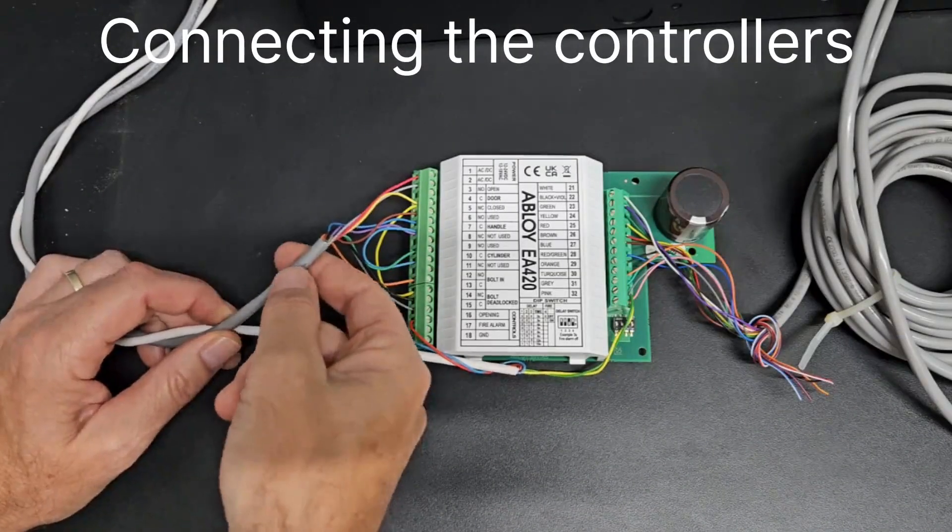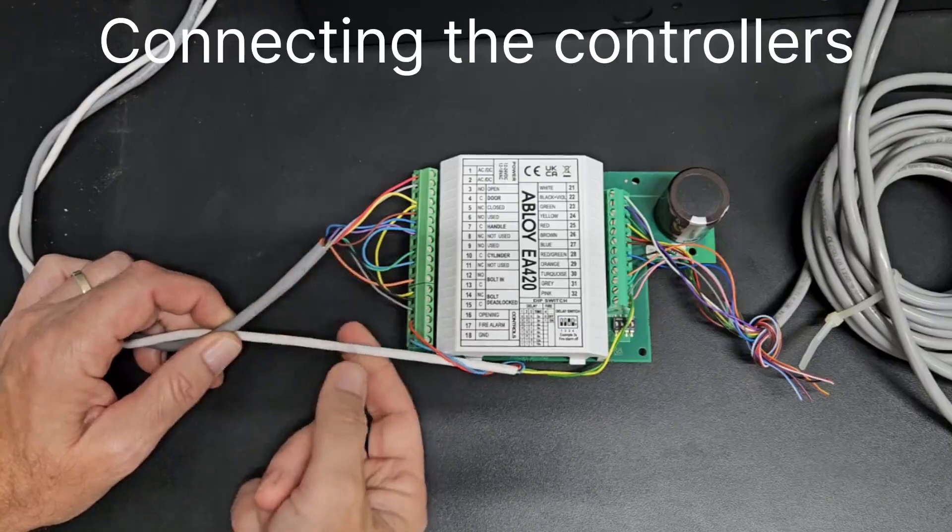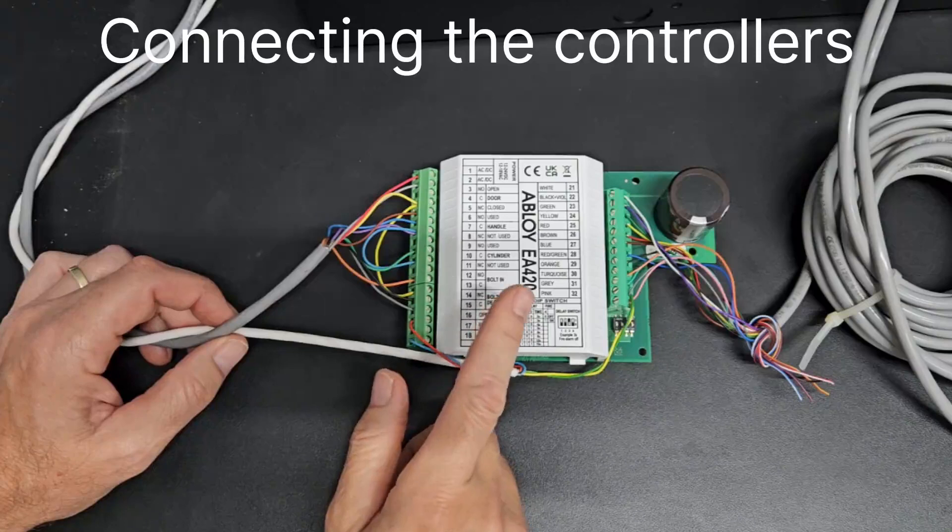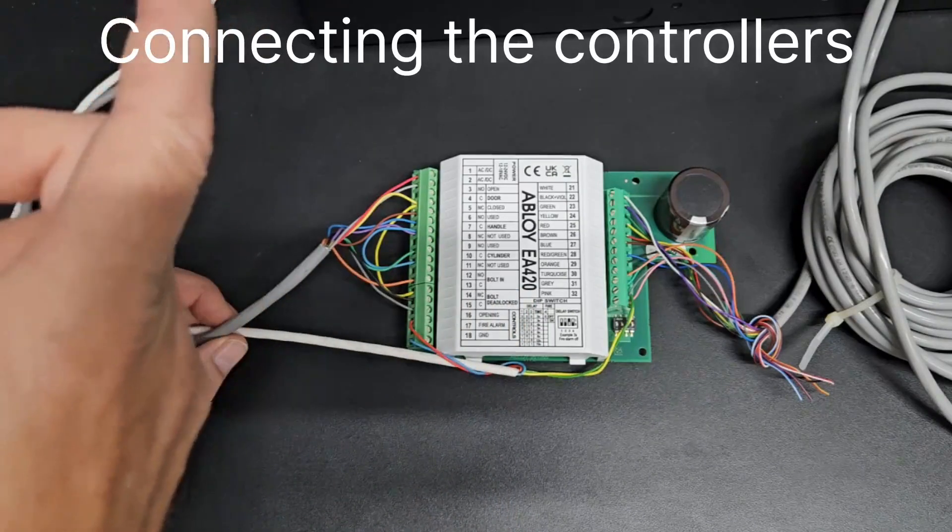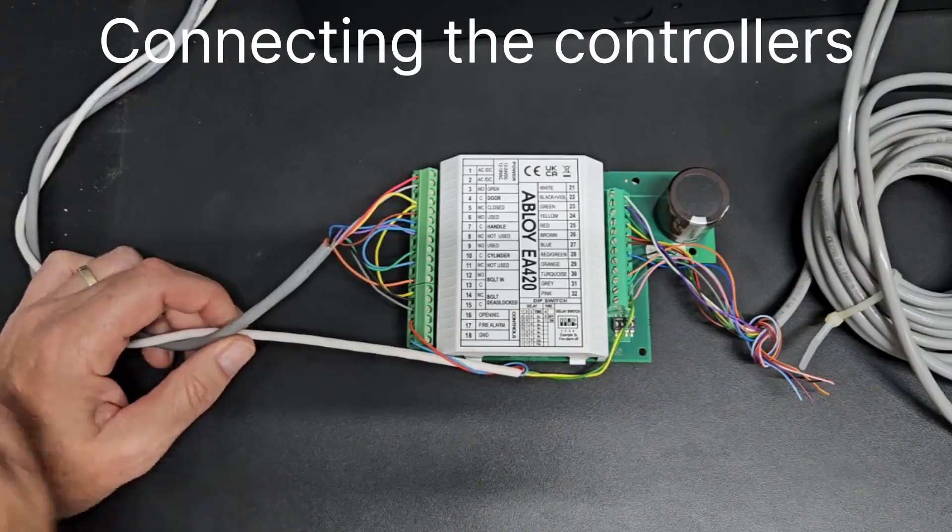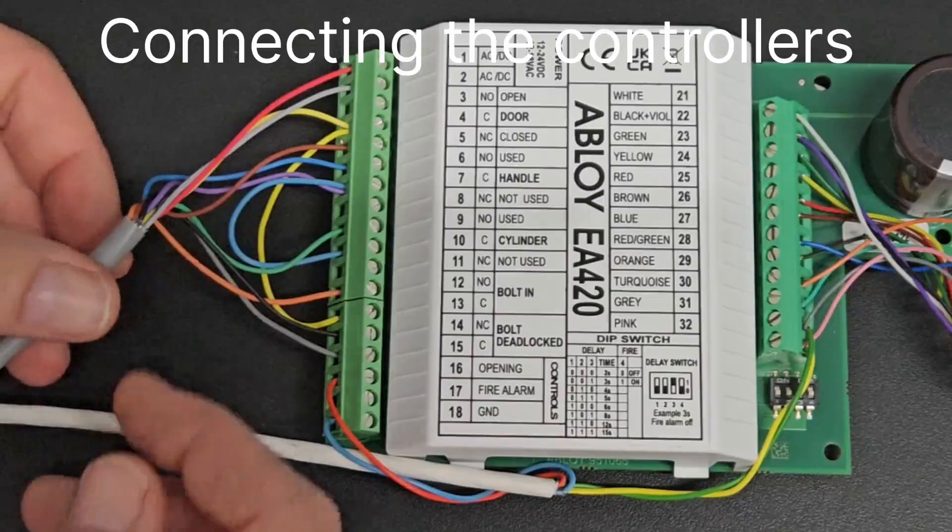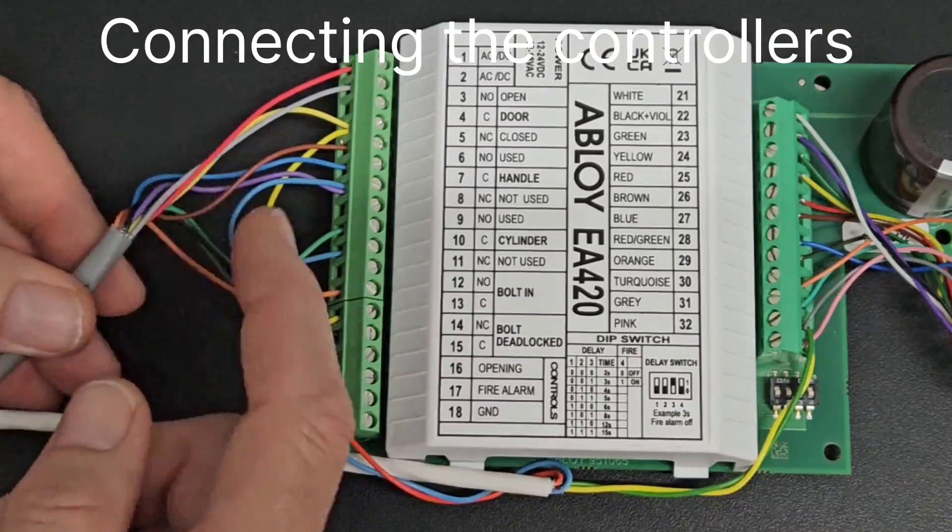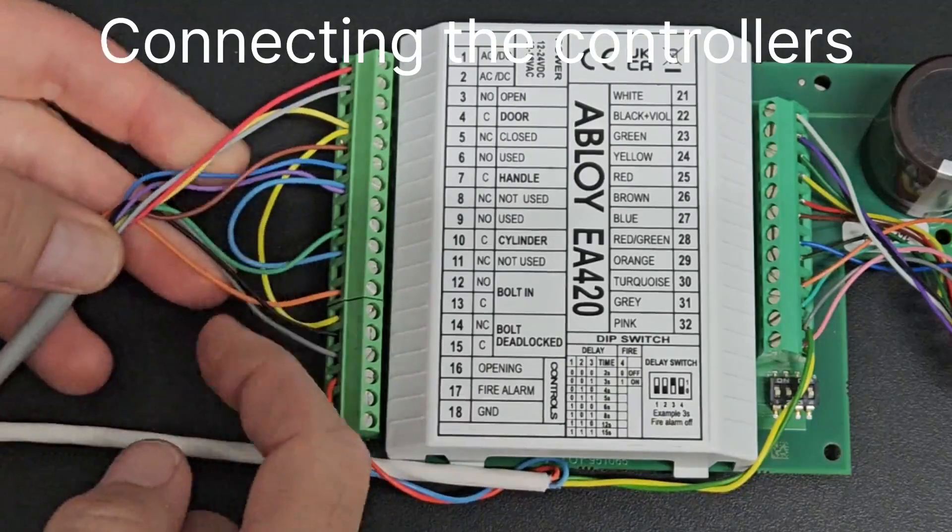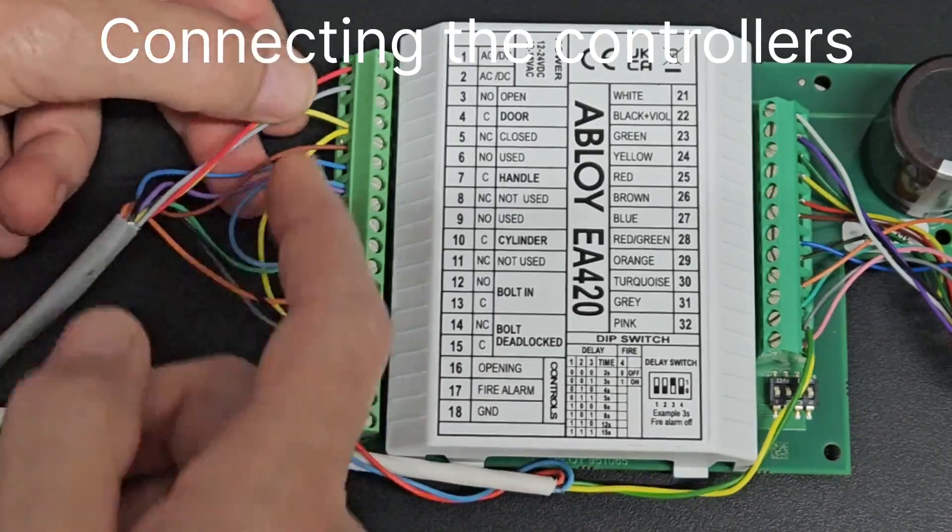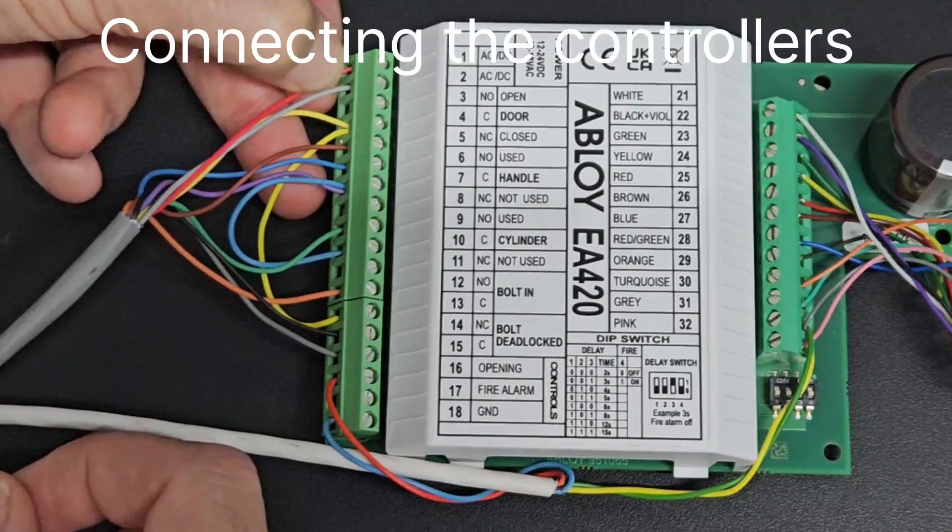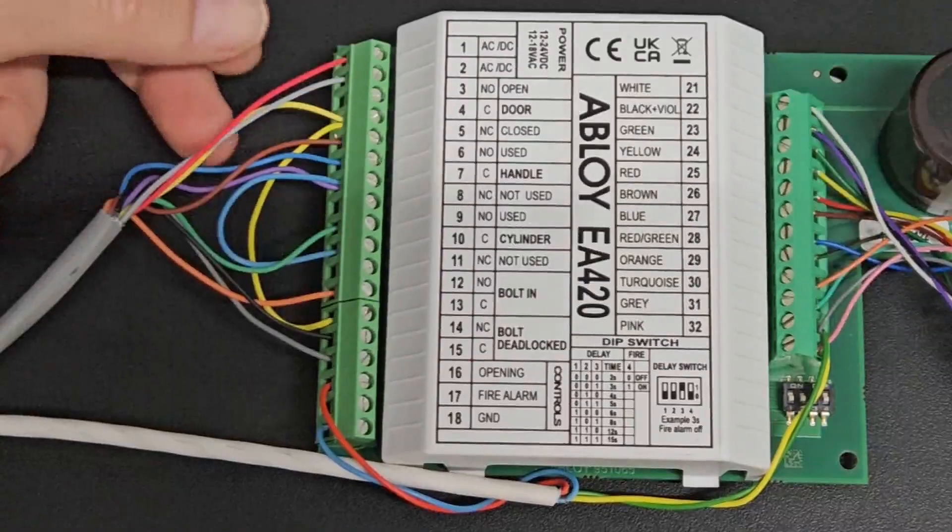You'll need to cut a length of 10-core data cable and 4-core data cable long enough to reach from the EA420 to the RTRT2EL. Leave an extra 60 or so centimeters. Strip back the outer sheath on both the 10-core and the 4-core cables to reveal 7 or so centimeters of the colored wires. And strip the ends of the colored wires back so that 5mm of copper is exposed.